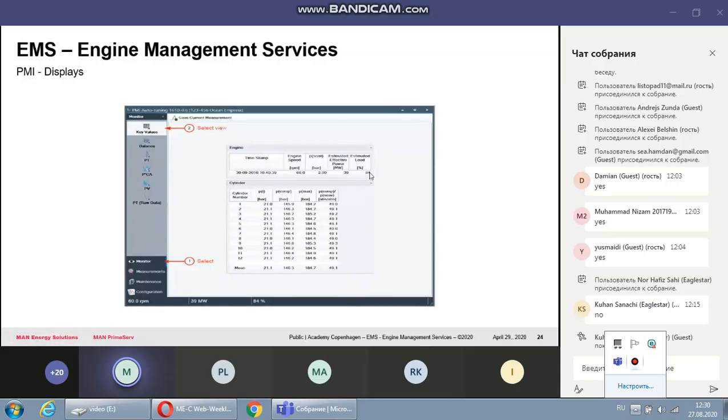And how do you bring this up? How do you get it? You add the offset. Fuel quality offset. Excellent. So you need to go to the screen called fuel quality offset, and adjust from the calculated value. Let's say you put the new fuel with the calorific value, density, and temperature. You got a calorific FQS of +5.